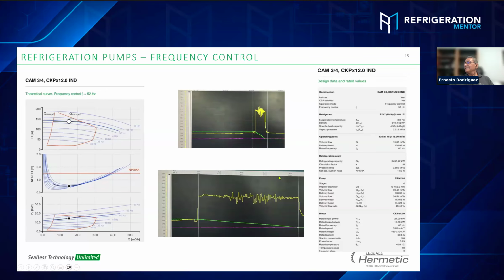In this situation, the technicians started increasing the hertz to 56 hertz. They showed me the curve on the pump, and we have this flashing. I said, what is that? They enlarged the curve, and we have this. This is flash gas inside the pump. I said, you guys, don't do that. Go back to 52 hertz. You can see right here, the motor is set for 30 amps. 30 amps is the maximum. This is the nameplate of the motor. That is the 30 amps. You check the amp meter, and it's very close to the maximum capacity of the motor. That is a big problem.